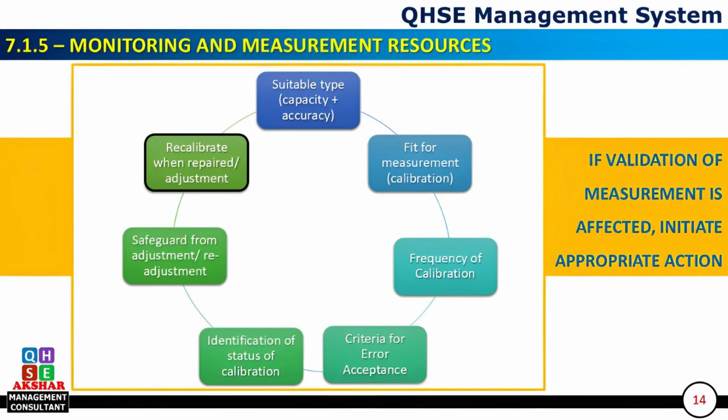If the monitoring and measuring resource is repaired either internally or externally during maintenance, it shall be recalibrated even if the date of calibration is not due.